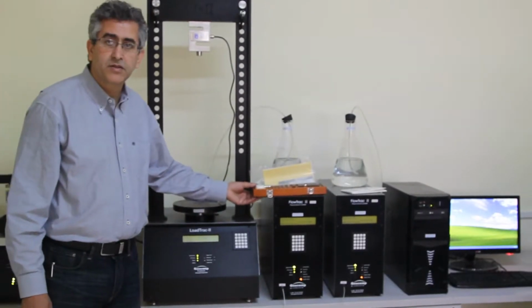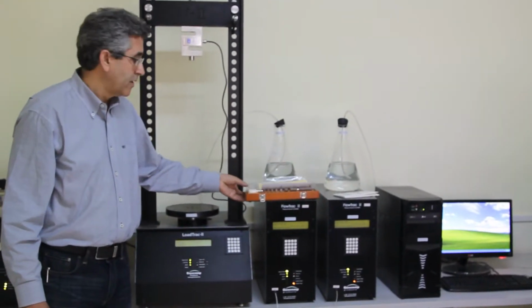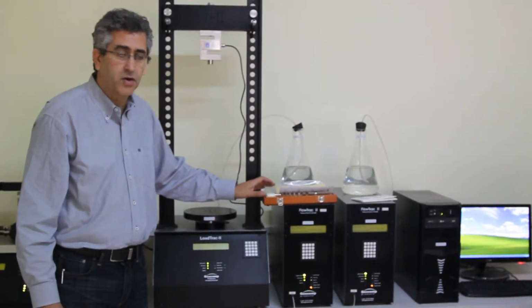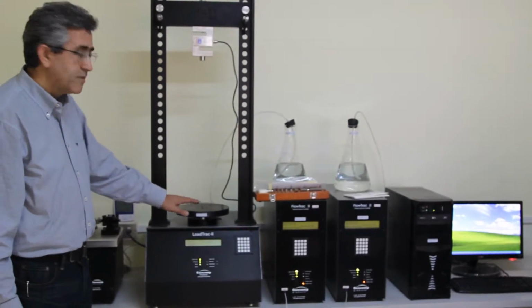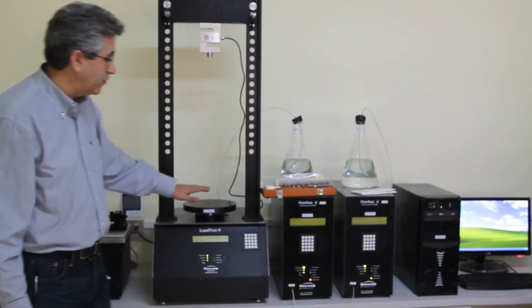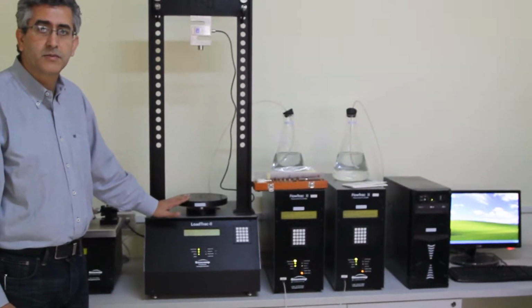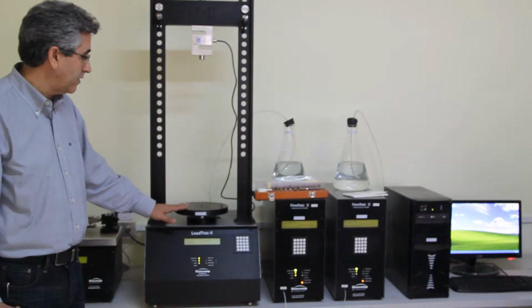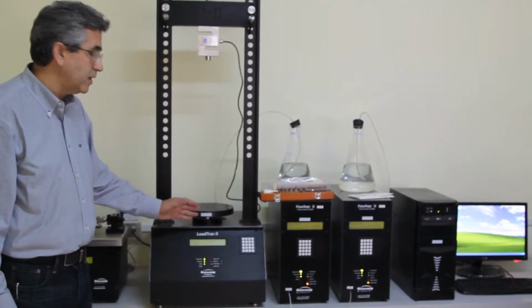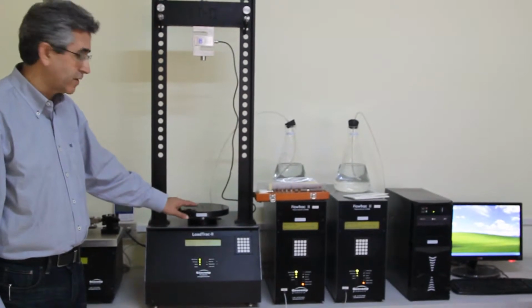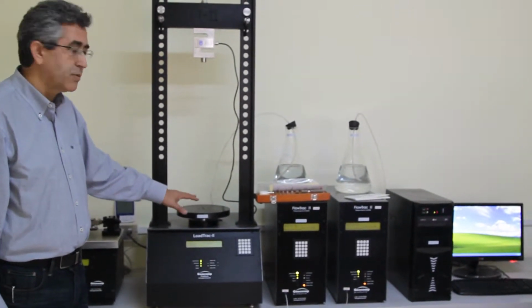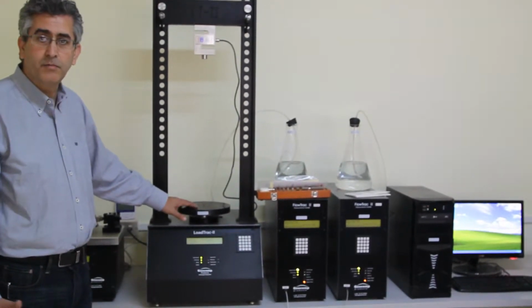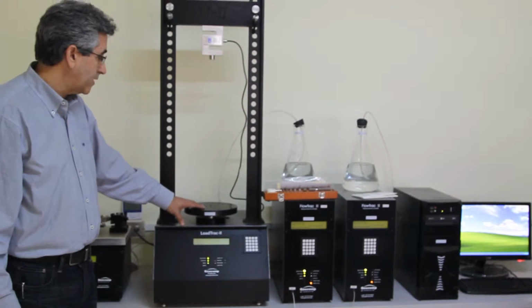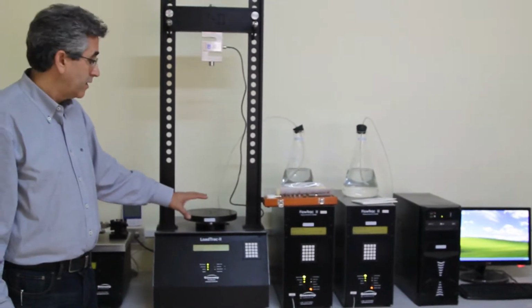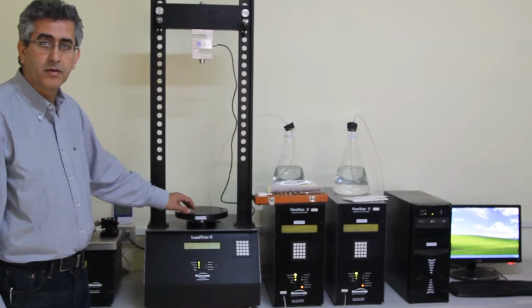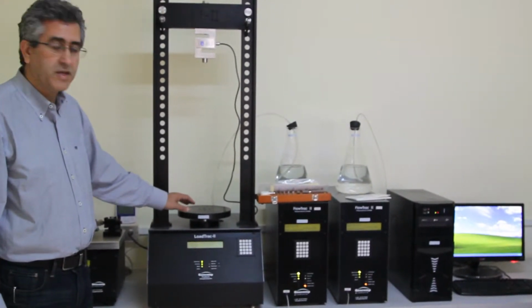Now that we have our calibration devices ready, which are the gauge blocks, and I explained it in the first part of this calibration procedure, step by step, the next step is our displacement sensor. We need to move the platen to a position that corresponds to about the middle range of our displacement sensor. And to do that, we need to raise the platen. Depends on where the platen is located, but we need to raise it. That will correspond to a microstepper reading of about 800 to 900,000 steps, or in terms of counts reading or bit reading, we need to be about 40,000 counts.